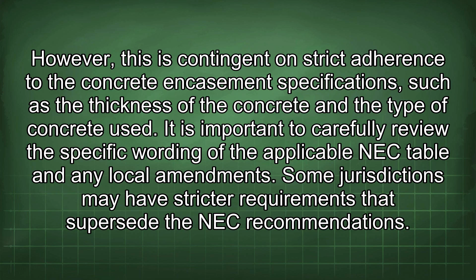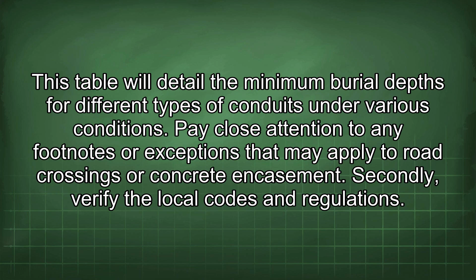Firstly, review the specific NEC table that applies to the installation. This table will detail the minimum burial depths for different types of conduits under various conditions. Pay close attention to any footnotes or exceptions that may apply to road crossings or concrete encasement. Secondly, verify the local codes and regulations. Local jurisdictions may have amendments to the NEC that impose stricter requirements. Contact the local electrical inspector or building department to confirm the applicable codes for the specific project location.